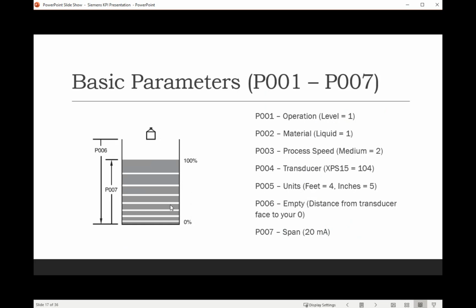Number 3, process speed. Medium is the most common right now. Put a 2 in there. And then number 4, you have a transducer. It has ability for all the Siemens transducers, so XPS 10, 15, etc. P005, what units? Feet, inches, meters, millimeters. Then the 2 probably most important parameters that we need to enter are your empty distance, which is your distance from the transducer face to your 0, and then P007 is your span, so whatever you'd want your 20 milliamp to be set to.